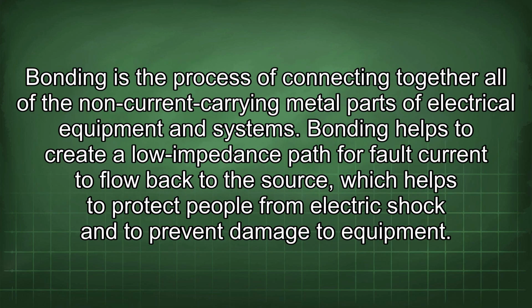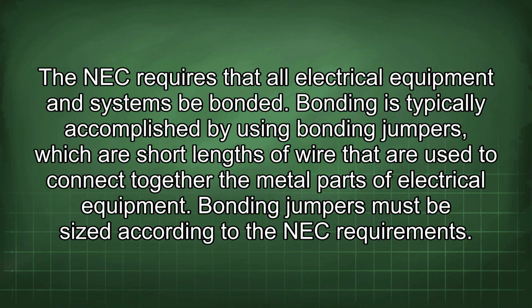Bonding is the process of connecting together all of the non-current carrying metal parts of electrical equipment and systems. Bonding helps to create a low impedance path for fault current to flow back to the source, which helps to protect people from electric shock and to prevent damage to equipment. The NEC requires that all electrical equipment and systems be bonded. Bonding is typically accomplished by using bonding jumpers, which are short lengths of wire that are used to connect together the metal parts of electrical equipment.